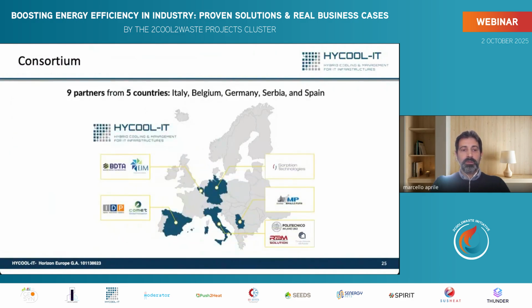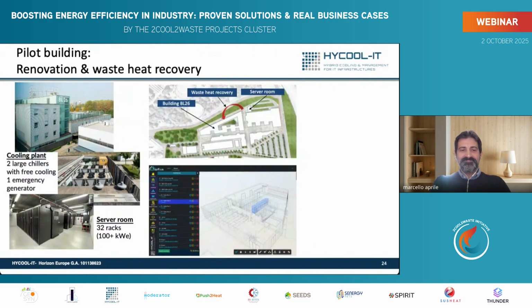Sorry, I need one second more on the previous slide. But the most important thing to mention is that we are performing waste heat recovery here, so the server room can provide heat to a nearby building. With that, we count on saving about 20,000 euros per year, and this saving is enough to justify the investment in a waste heat recovery system.